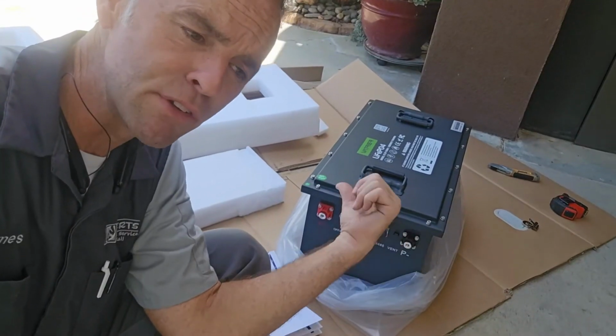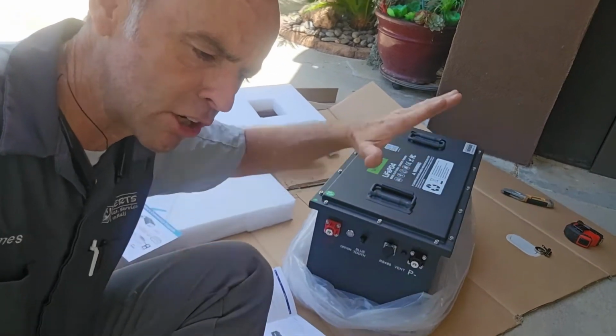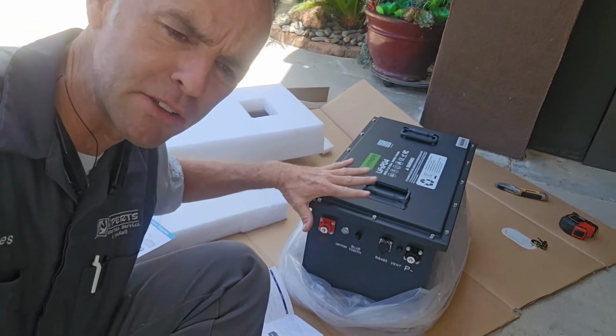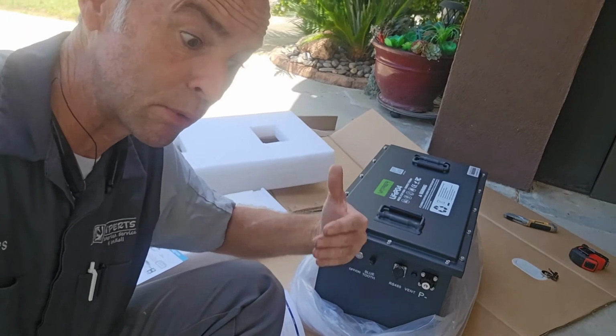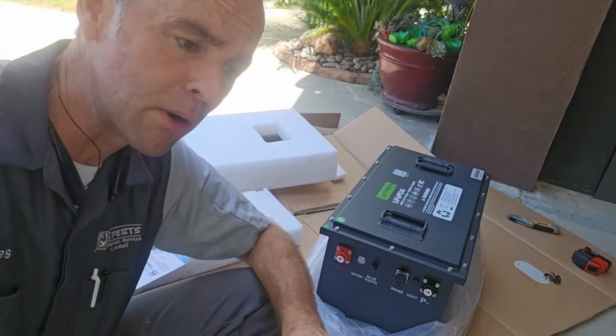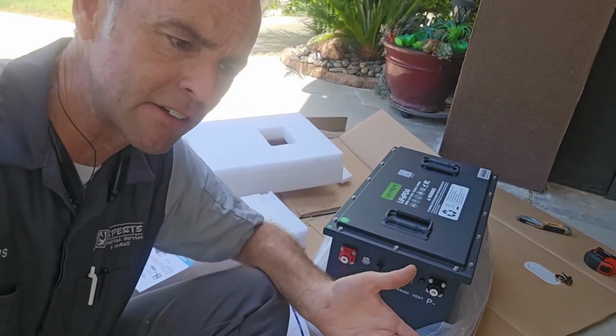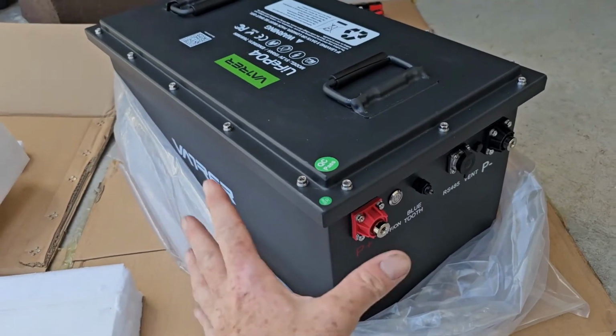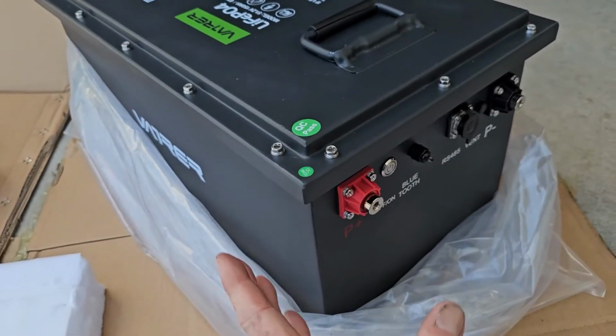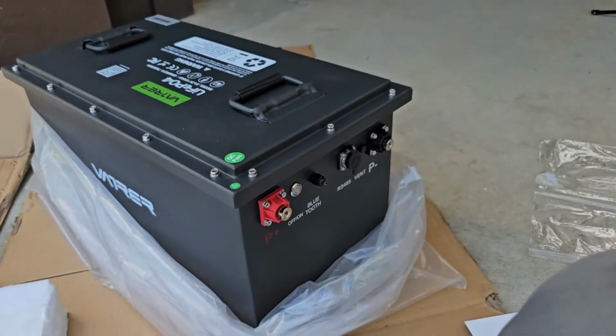It's important to note that even though this has a low temperature cutout from the charger on the BMS, there are no heaters built into it. So if you're going to store it outside where it will be below freezing, you might want to consider getting a heater pad to put underneath it, which should work pretty well with this steel case, being able to absorb that heat.